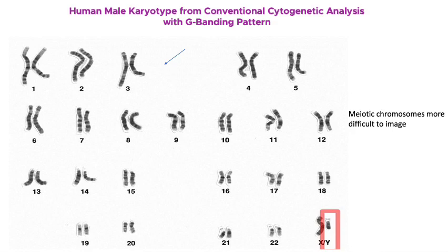However, instrumentation came about for amniocentesis, primarily, that automatically took pictures from slides, and you could do multiple cells in that case, and then would rearrange using a cursor each chromosome, and then would align them 1, 2, 3, 4, 5, etc., depending upon the chromosome number, automatically. And this was a huge labor-saving device, and you could do multiple cells, because if one cell from an amniocentesis was abnormal, you had others to look at at the same time, so you could assess the relative abundance of normal and abnormal cells.